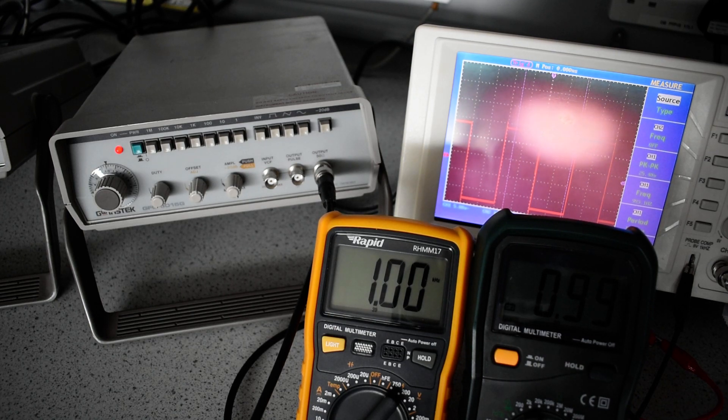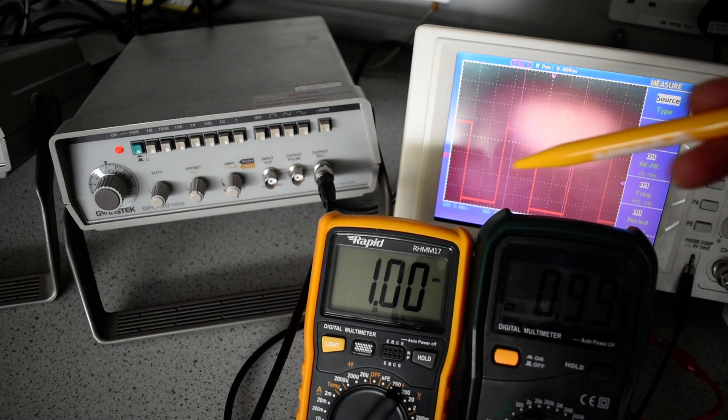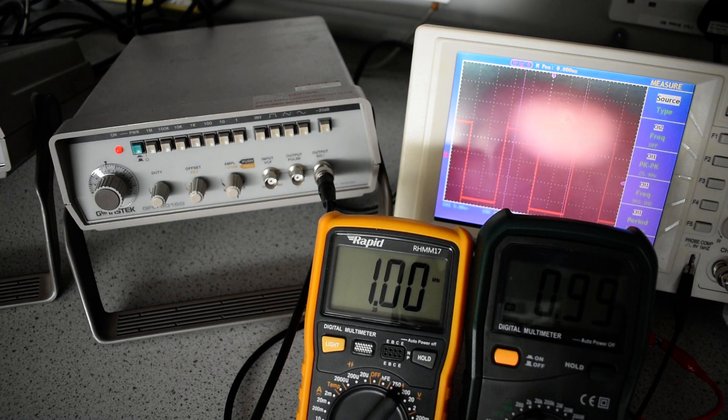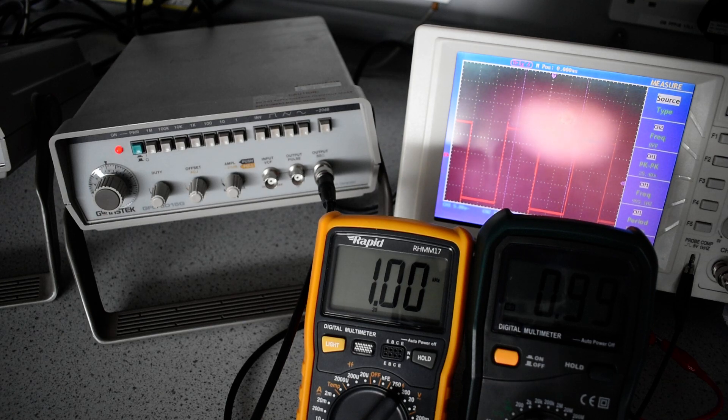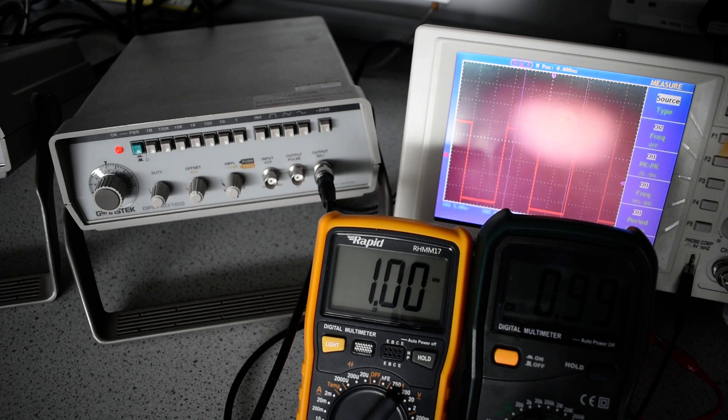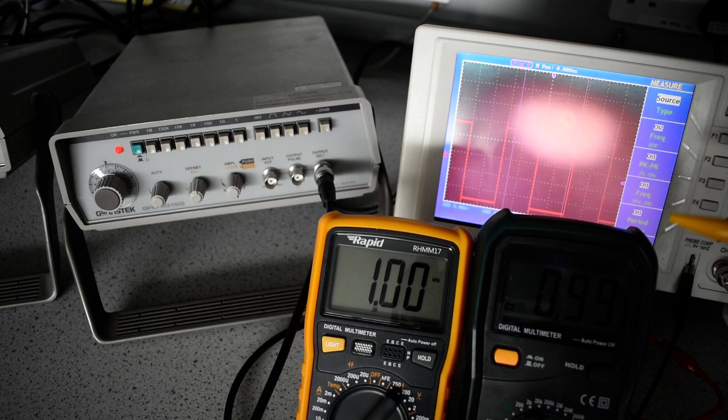These three different pieces of test equipment do read very similar values. So that would give a confidence level that they are accurate. How do we know what accuracy we have on test equipment? They should have a calibration certificate. The only one that we can be sure about is the Rapid RH MM17, which is a new meter a couple of months old.